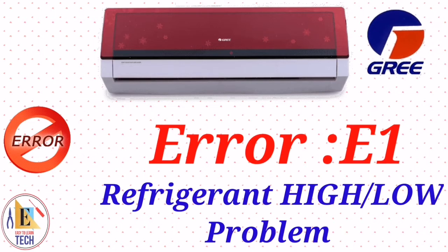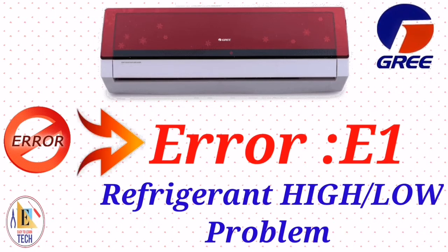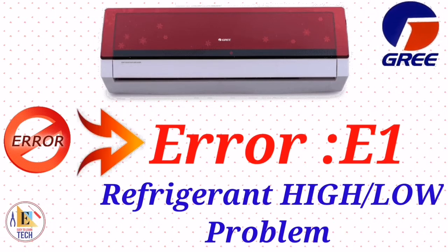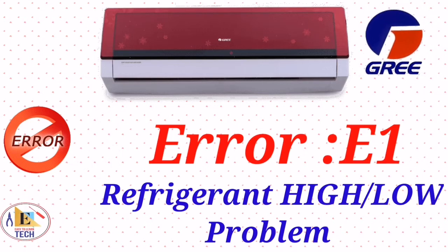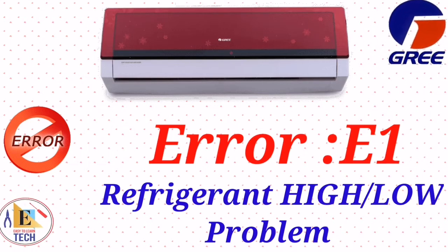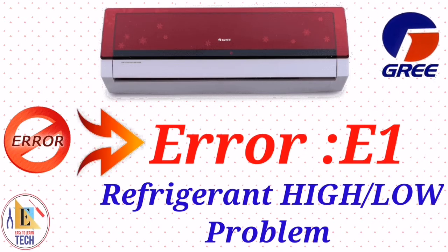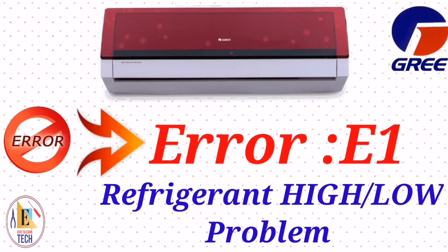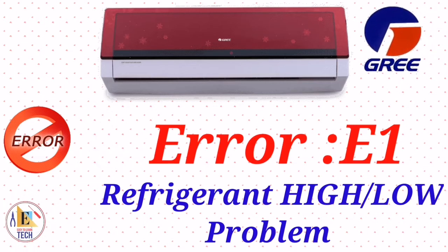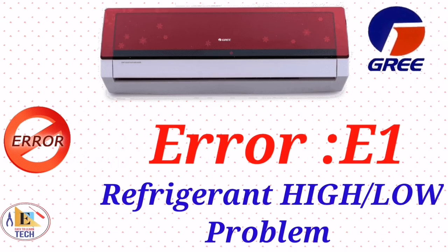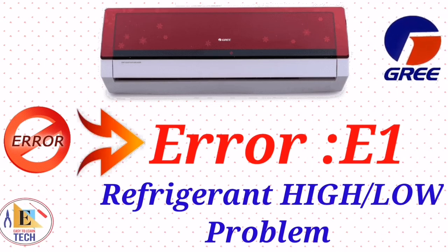And if the refrigerant is high, our back pressure is high, it means during the installation or during the maintenance, our technician has put in too much refrigerant. Then you have to release some of the refrigerant and you will get the refrigerant to normal pressure, and the error E1 will be solved and your unit will be in working condition.